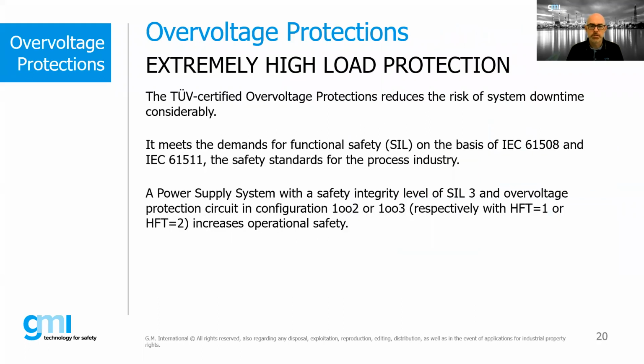In the next slide, we have some considerations about overvoltage protection. Overvoltage protection, as mentioned above, is fundamental in a safety power supply system because it allows us to reduce the risk of system downtime considerably. In fact, if one of the safety power supplies fails in an overvoltage condition, the protection brings the output to 0 volts, allowing the other power supply system to continue working correctly without the risk of sending the system to shutdown. A standard power supply without protection would cause a shutdown of the whole plant with the consequent repercussions on productivity and cost. A SIL3 level power supply system with overvoltage protection is able to increase operational safety and productivity and reduce costs.